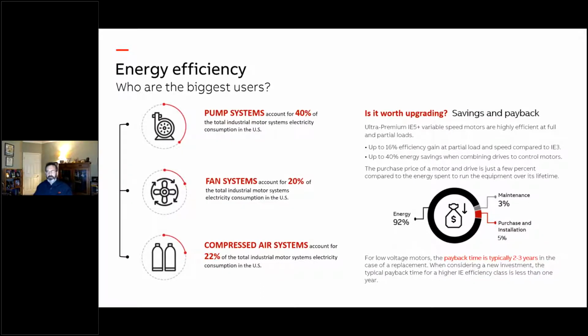The other aspect of it, and if you're looking at this and go, well, what does this say? You talked about energy efficiency, you talked about energy efficiency in building systems. Why is it so pertinent that pump systems, fan systems, and compressed air systems are the primary consumer of electrical energy within those systems? Normally, when you talk about efficiency for a motor at least, you talk about it at full load and full speed. But as you know, pumps, fans, and compressed air systems, at least the recirculating fans and compressed air systems, do not operate at full load and full speed. They're designed for peak capacity, but most of the time they're running 80% speed or lower. 80% speed is 52% load, and it could be even lower than that. So what you really want to look at is, what kind of efficiency gain are you getting at those partial load conditions?